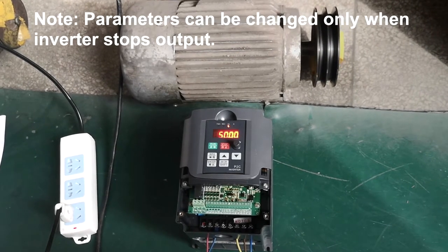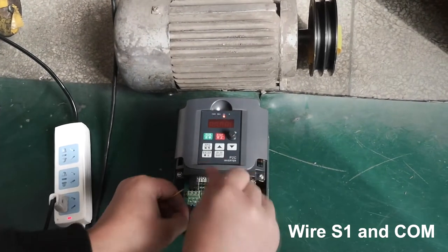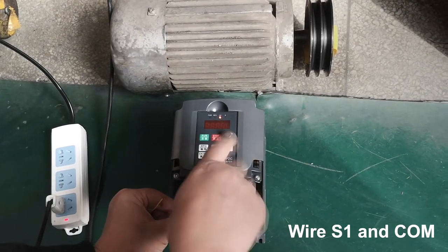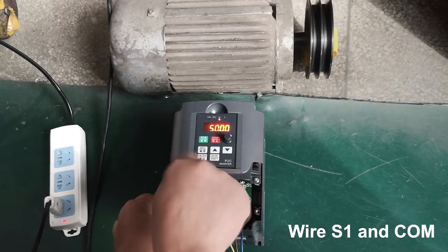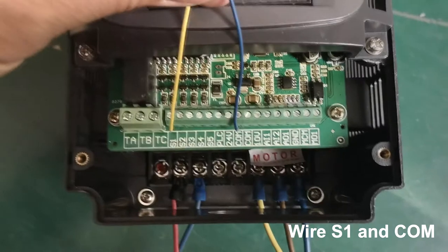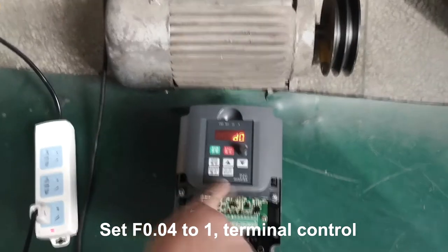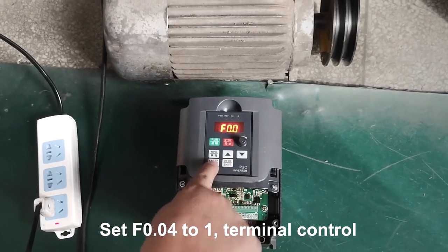Parameters can be changed only when the inverter stops output. Wire S1 and COM, and set F0.04 to 1 for terminal control.